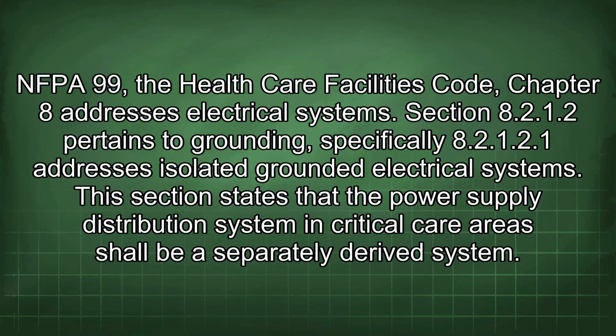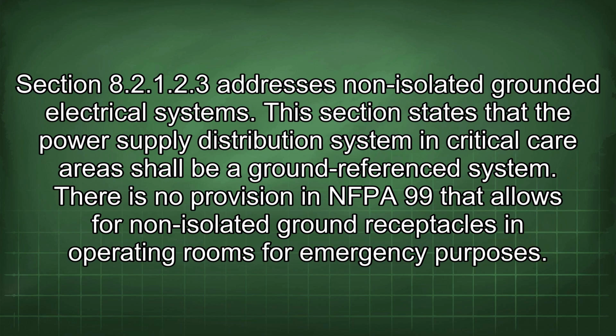NFPA 99, the Healthcare Facilities Code, Chapter 8 addresses electrical systems. Section 8.2.1.2 pertains to grounding, specifically 8.2.1.2.1 addresses isolated grounded electrical systems. This section states that the power supply distribution system in critical care areas shall be a separately derived system. Section 8.2.1.2.3 addresses non-isolated grounded electrical systems. This section states that the power supply distribution system in critical care areas shall be a ground reference system.